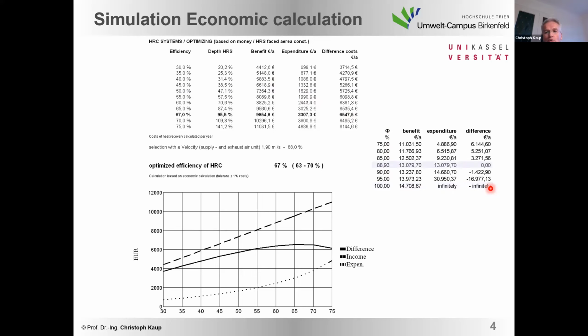So the point of no return, the latest point where heat recovery makes no sense, is when the benefit of the heat recovery reaches the same size as the expenditure. In that example, you have a benefit at 88.9% of efficiency of roughly 13,000 euros, and you have to invest 13,000 euros. So at the end, the net income of the heat recovery would be zero. So at that point, you will have the same situation as if you don't install a heat recovery system. Then you have no benefit, no expenditure. At the end, you have zero. So it's the same situation. But that makes no sense.